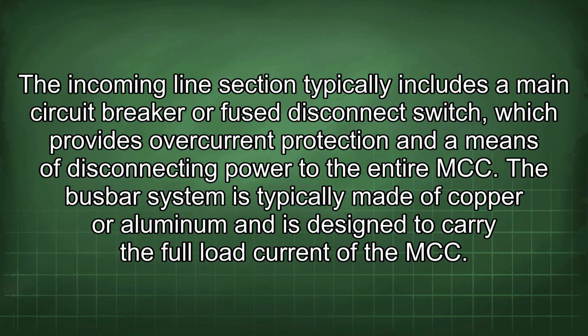The incoming line section typically includes a main circuit breaker or fused disconnect switch, which provides overcurrent protection and a means of disconnecting power to the entire MCC. The busbar system is typically made of copper or aluminum and is designed to carry the full load current of the MCC.